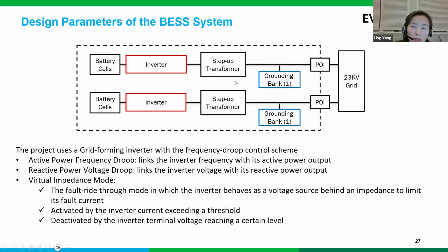At the early stage, as I said, we encountered quite a lot of system instabilities, and we spent a lot of time tuning the inverter control parameters. We also played with the grounding bank impedances and configurations, trying to make the system stable and making sure the system is effectively grounded. Some of the parameters we changed and tried to optimize, not only but including, are the droop settings as well as the virtual impedance mode.